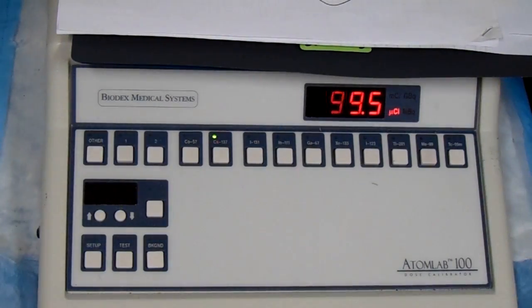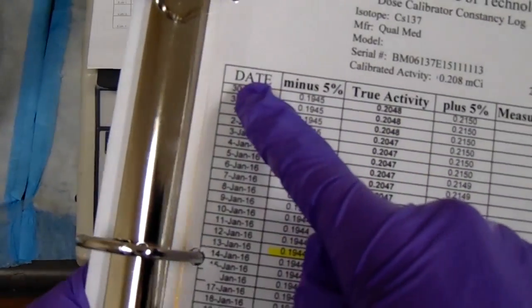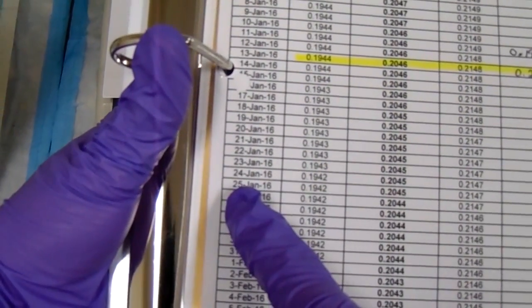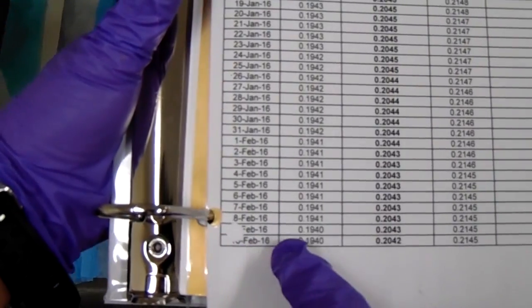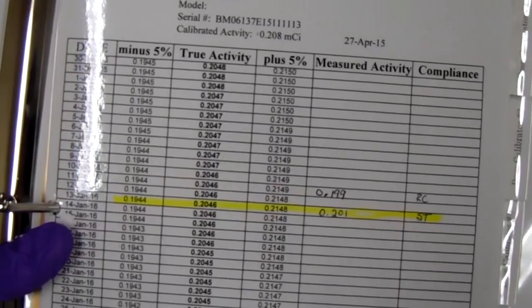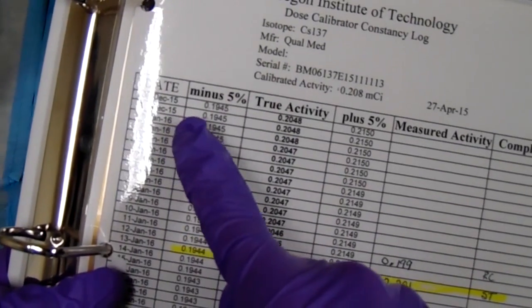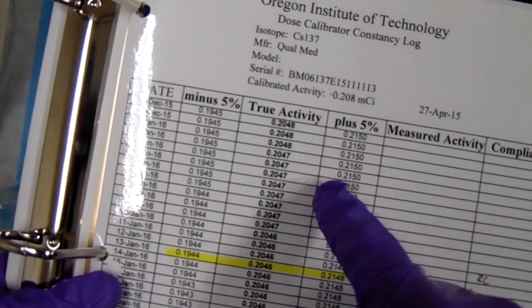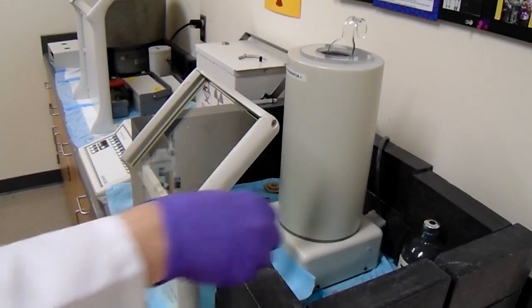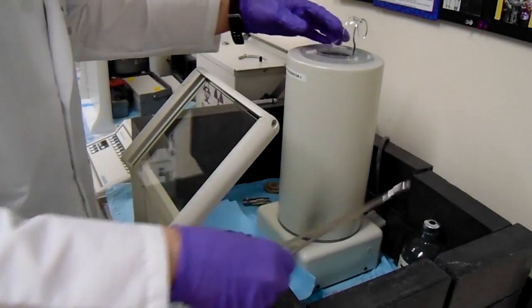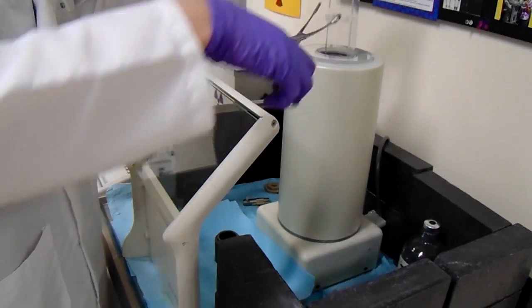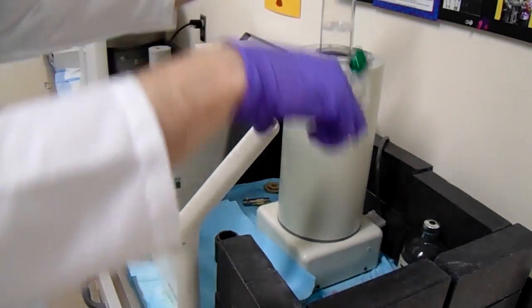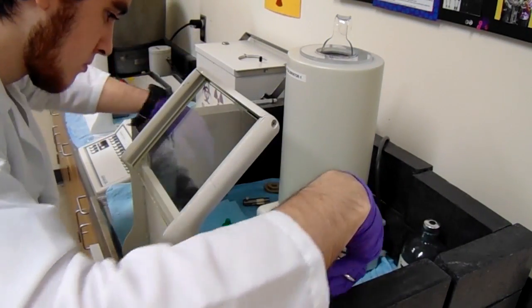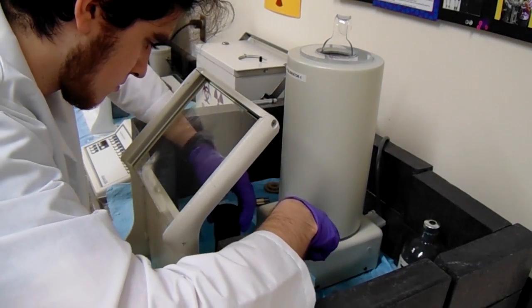Now you're going to take this number and record it in your log under your calibrator notebook and go to today's date and record this number in the measured activity tab. And you're going to record it in millicuries as opposed to the microcuries that the display says, and as long as it's within plus or minus 5% of the actual activity the cesium source should be, your calibrator is working fine. Now you're going to take the source and use your tongs, put it back in its lead pig, and now you're done doing your constancy on your calibrator.